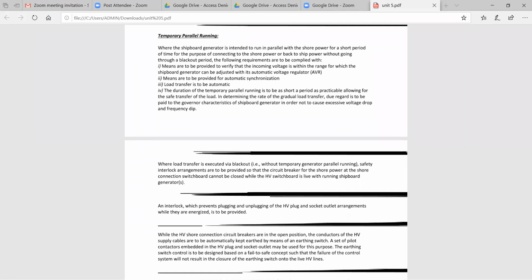It means we verify that the incoming voltage of a system is equivalent to the automatic voltage regulator setting. So how can you vary the voltage? By varying the field excitation of an alternator. If the field excitation is varied, the flux value varies. If the flux varies, according to the concept of the EMF equation, the voltage value is also boosted. So the parallel operation can be performed with the automatic voltage regulator along with the shipboard generator. So it can be mentioned in the first point.